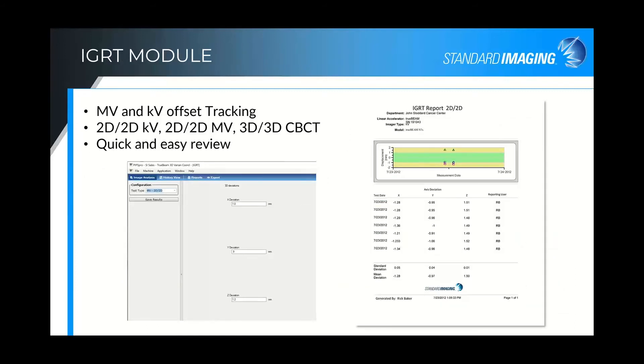The IGRT module is more of a data storage, warehousing, and trending tool than a specific test. We utilize a phantom similar to our Mimi phantom, which checks perpendicularity and coincidence of MV and KV imagers, and allows couch offset checks. The imaging performs 2D/2D matching with KV and MV, and 3D/3D matching with cone beam CT. You can enter the found X, Y, and Z deviations for a given day, then print a report showing deviations on a trend line or in tabular format.